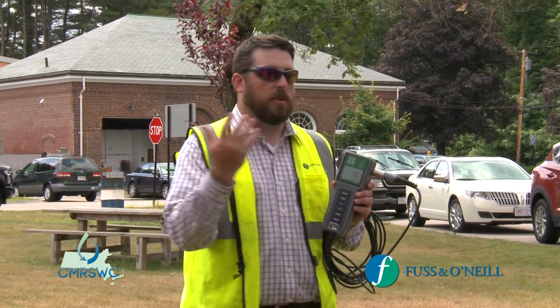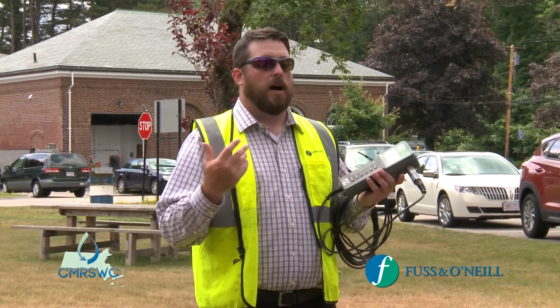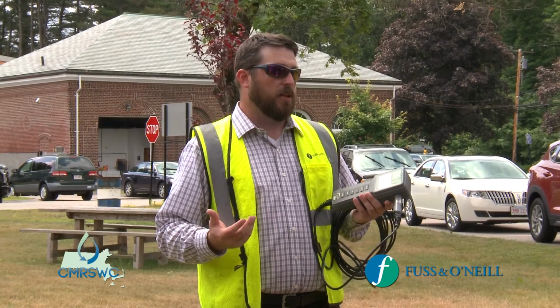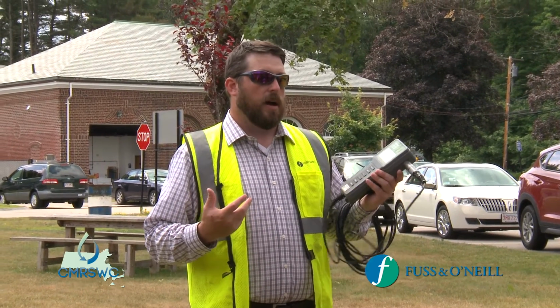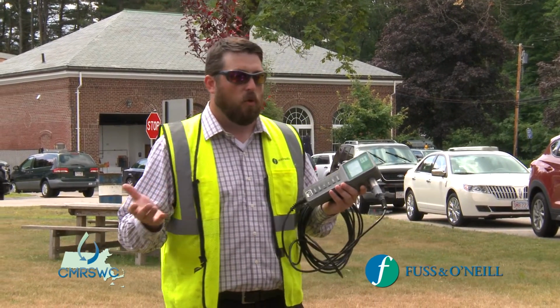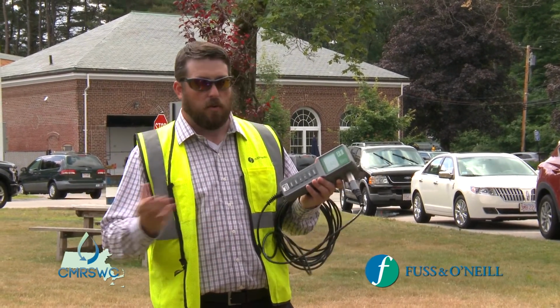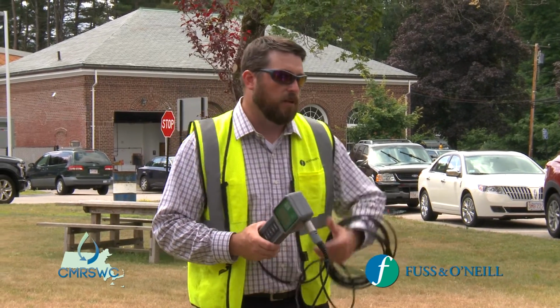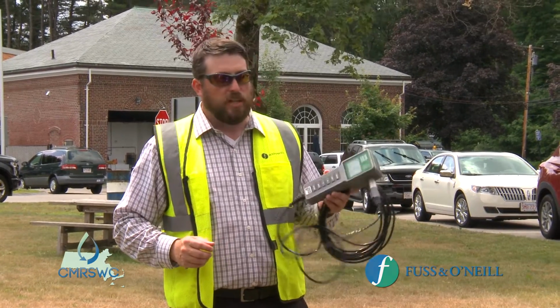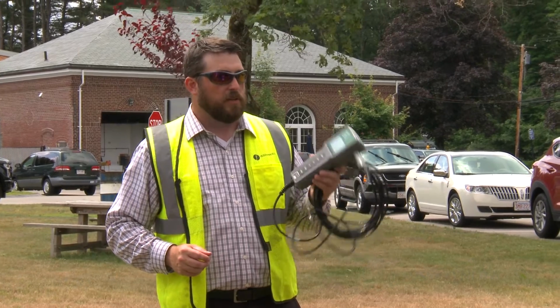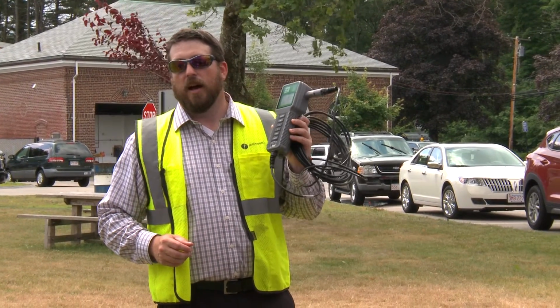This particular unit, when you read the user's manual, when you rent the unit, it comes calibrated. So you can just check the calibration with the standard that they supply you. If that's reading normal, then you go out and use it. You also have the standard there to calibrate if you need to calibrate as well. Bring the user's manual with you in the field. Some people forget to do this.